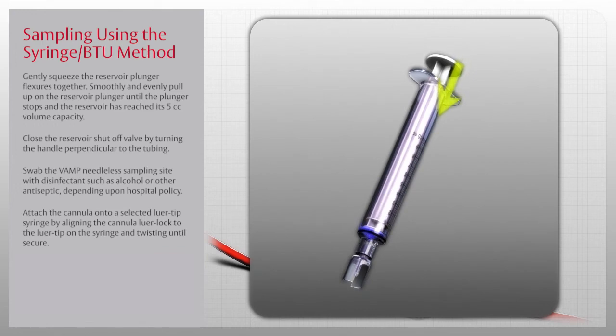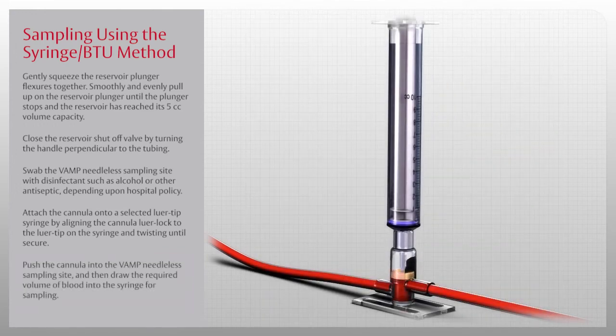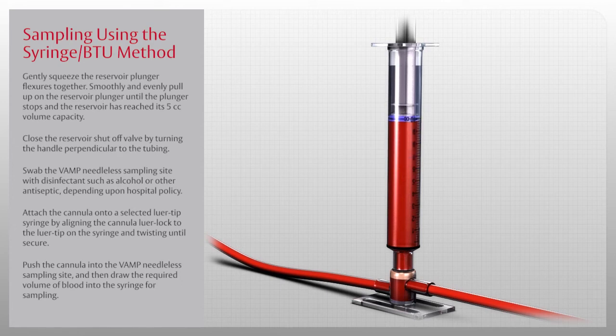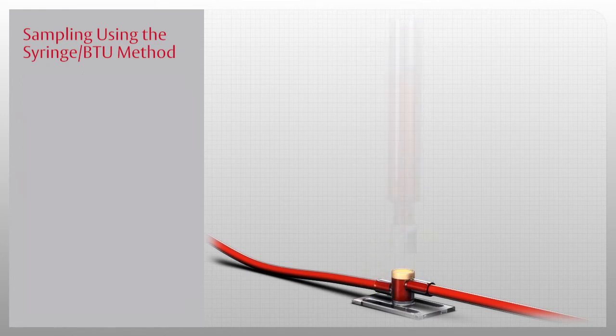Ensure that the syringe plunger is depressed to the bottom of the syringe barrel. Push the cannula into the VAMP needleless sampling site and then draw the required volume of blood into the syringe for sampling. Note: do not use a hypodermic needle through the sampling site. To remove the syringe cannula assembly from the sampling site, grasp the cannula and pull it straight out.